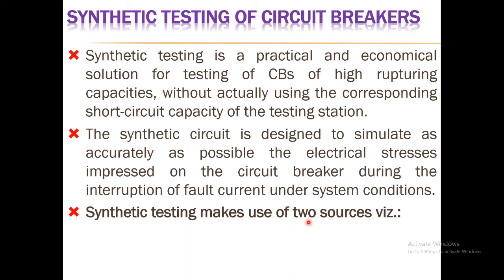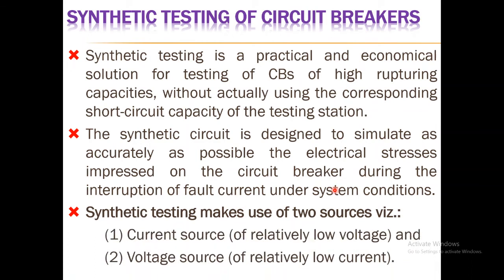The synthetic test makes use of two sources: one is the current source, which is of relatively low voltage, and the other is the voltage source, which is of relatively low current. In other words, these are known as the high current low voltage source and the high voltage low current source. These are the two sources generally found in a synthetic test circuit.